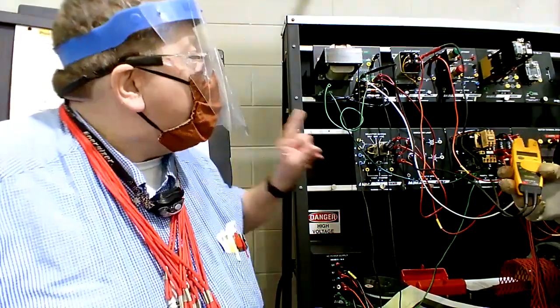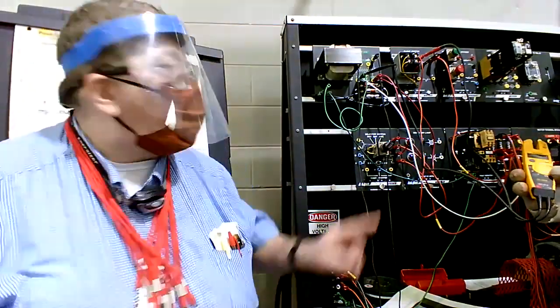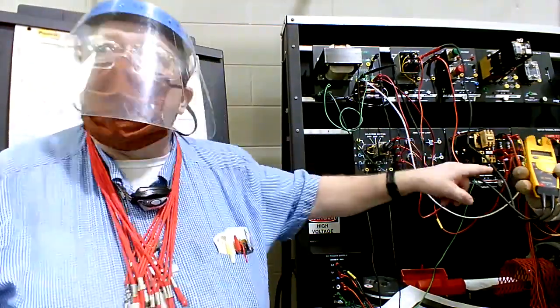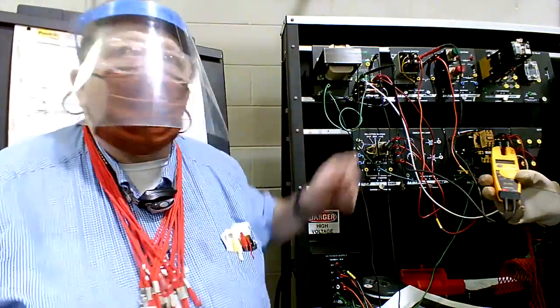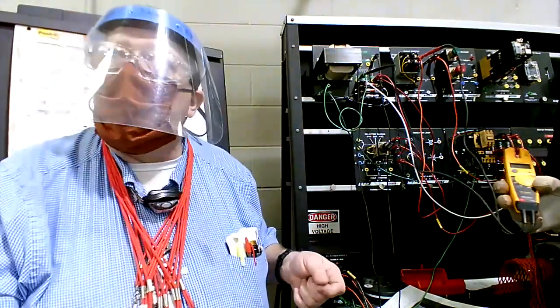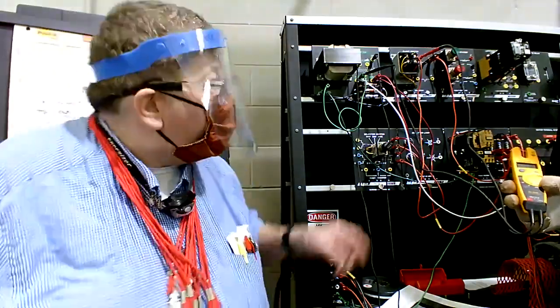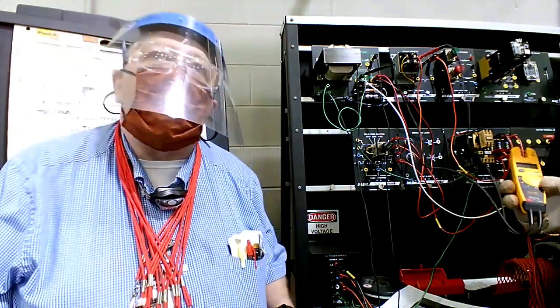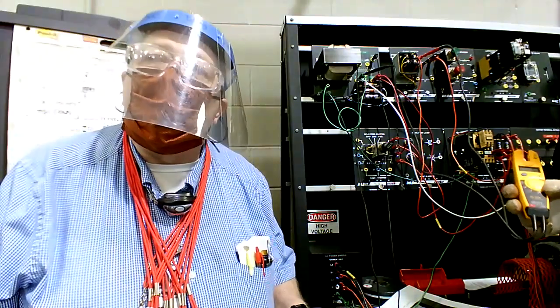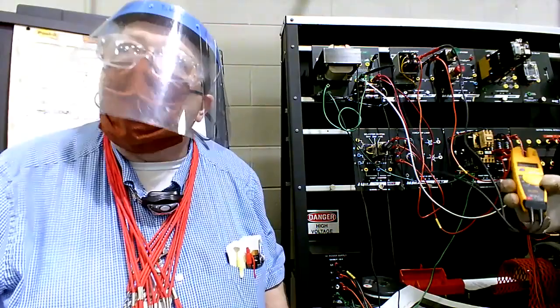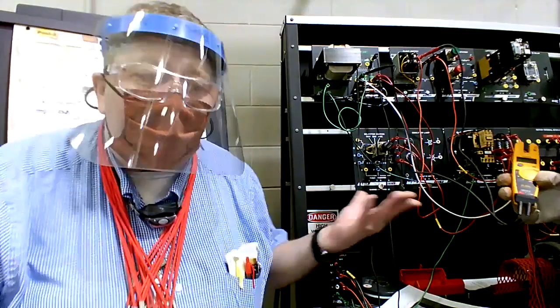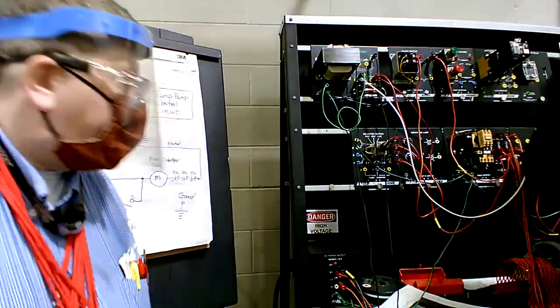But bottom line, you always do best if you use neutral for your reference point for the meter. Right. I'll throw it on neutral as a habit, and you will not go wrong. If you're using ground, it may be good or it may not, because of rusty connections, loose connections, corrosion, and stuff like that, and it can make you think you've got an issue that you don't really have. Or it could point to a bad ground connection. So that's basically all we're saying. Everybody understand? Yeah. Okay.